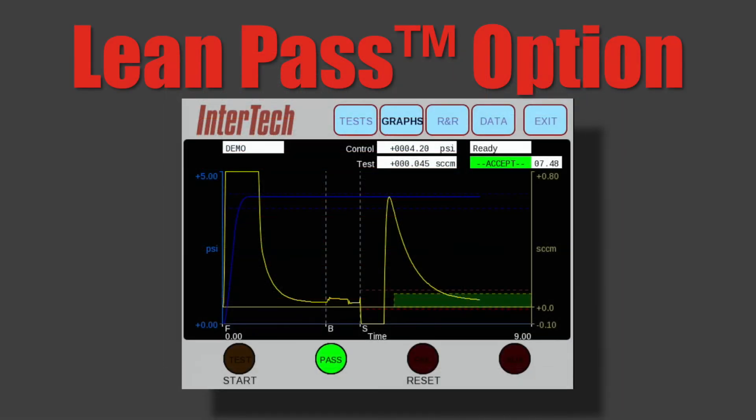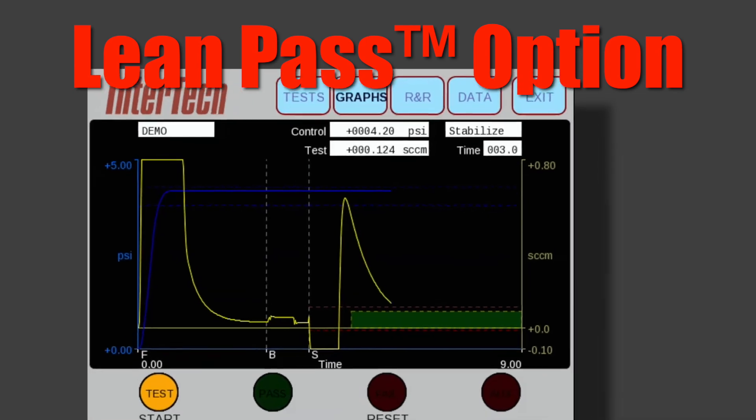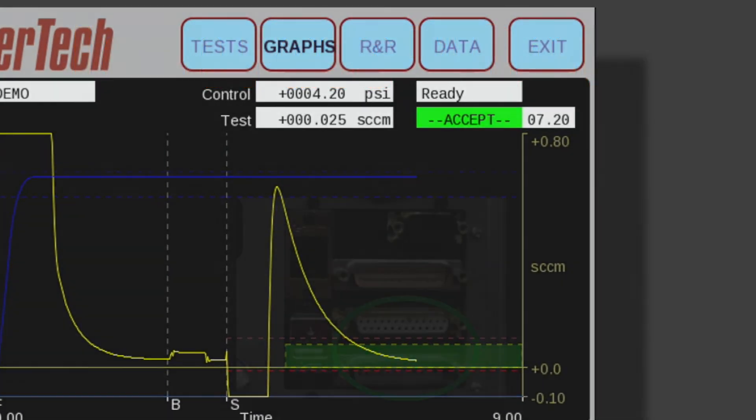Intertech's proprietary lean pass option can further reduce cycle time by passing an obviously good part as soon as its leak rate measured in real time during stabilization falls into the user's preset acceptable range.